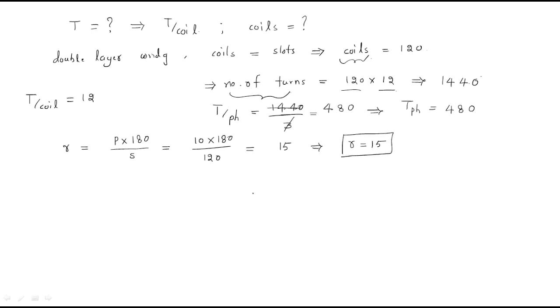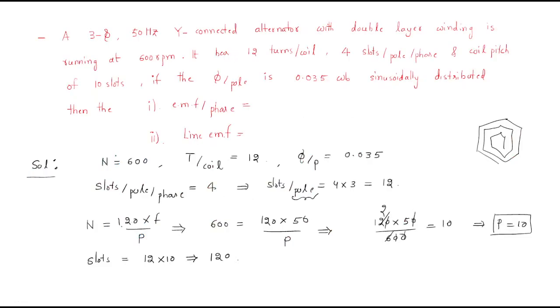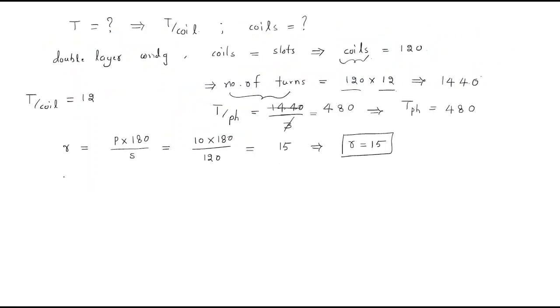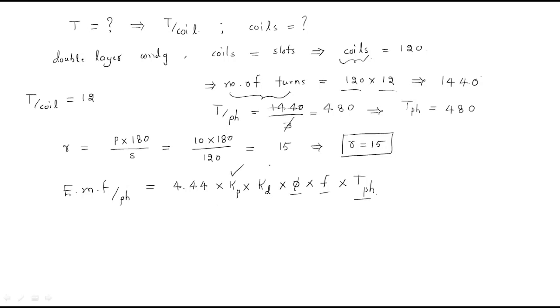Now we apply the EMF formula. The EMF per phase formula for an alternator is: E_phase = 4.44 × Kp × Kd × flux × frequency × turns per phase. We need the short pitch factor Kp and the distribution factor Kd. Kp = cos(α/2) = cos(15/2) = cos(7.5°) = 0.991.